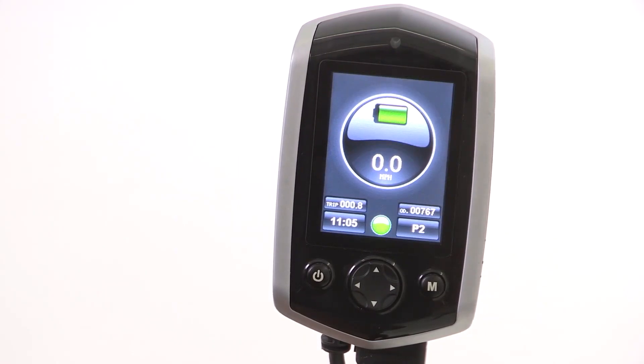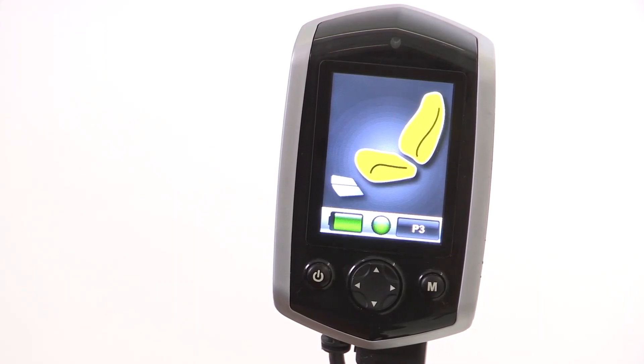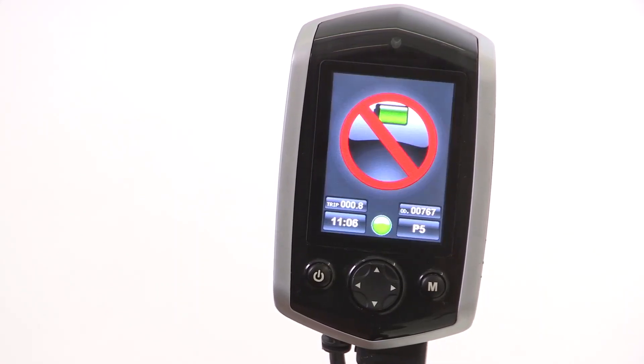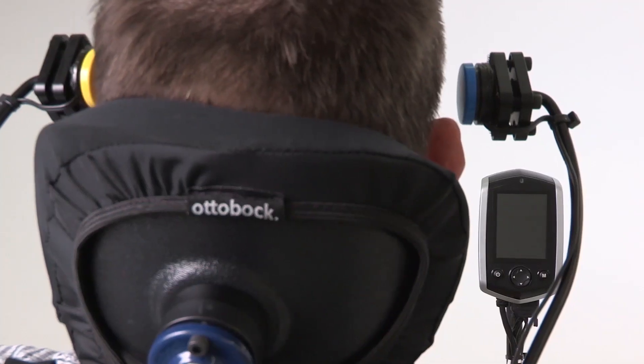In the current video the user has a Quantum R4000 powered wheelchair with Q-Logic 2 electronics. Several wheelchair parameters have been adjusted using the wheelchair programming software for smooth functioning of the head array system. The assembly consists of two head switches attached to an Otto Bock headrest using stealth swing away brackets.